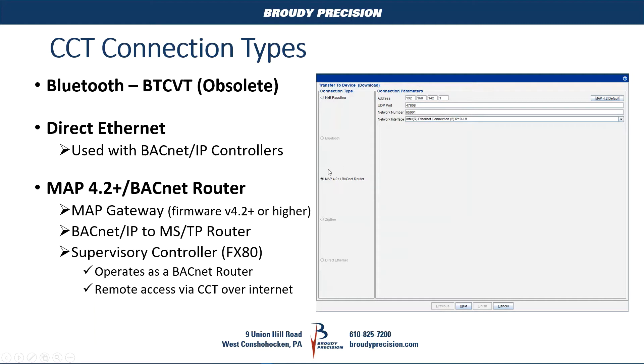When you choose the BACnet router or MAP gateway option, it'll work with MAP gateways at version 4.2 or newer, or BACnet routers — which could be a standard BACnet IP to MSTP router, or a supervisory controller, a JACE. The JACE basically becomes a BACnet router, and it would allow you to access the system remotely. If you have remote access to your JACE, you just need to add the BACnet port as a port forward to get down into it.